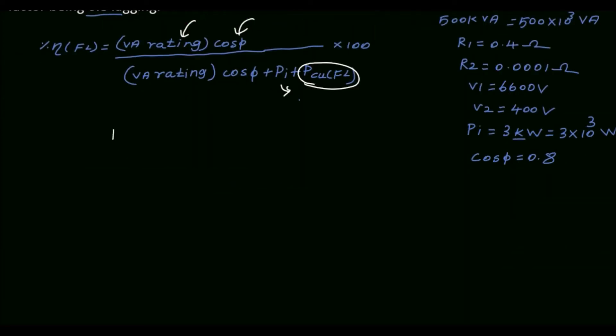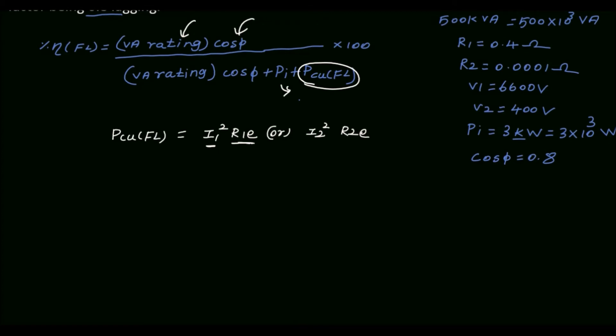First we have to find out the full load copper loss in order to find the efficiency. The full load copper loss can be found using either I1² R1E or I2² R2E, where I1 is the primary full load current and R1E is the equivalent resistance referred to the primary side, and I2 is the secondary full load current with R2E referred to the secondary side. We will use the formula I1² R1E.